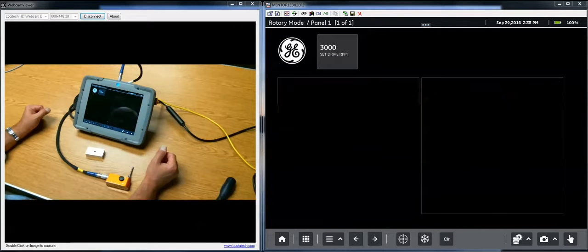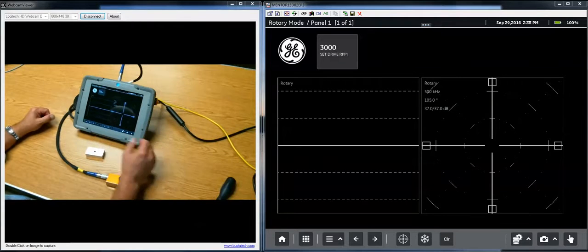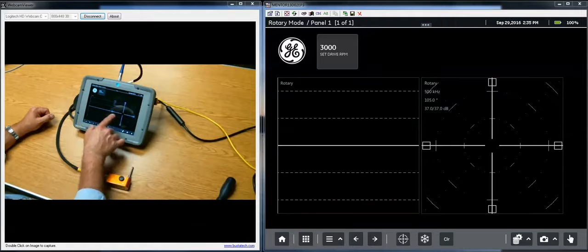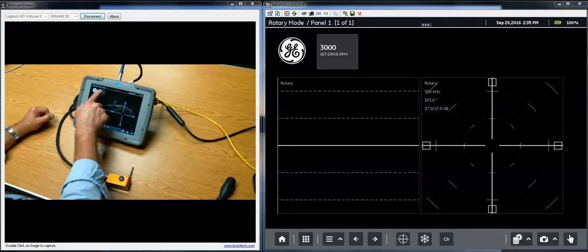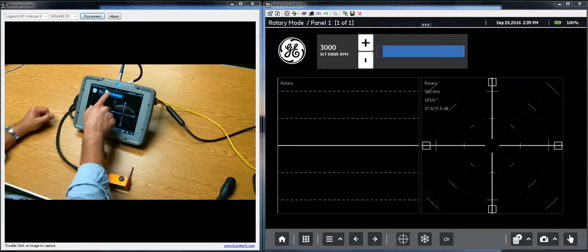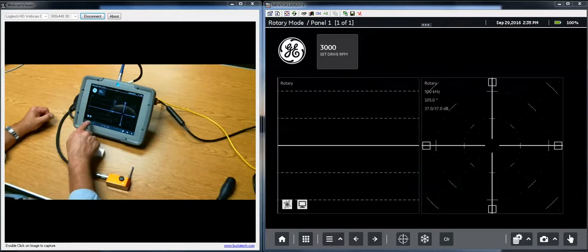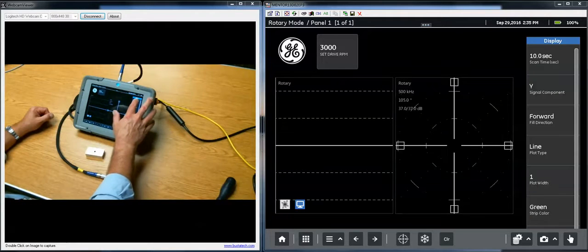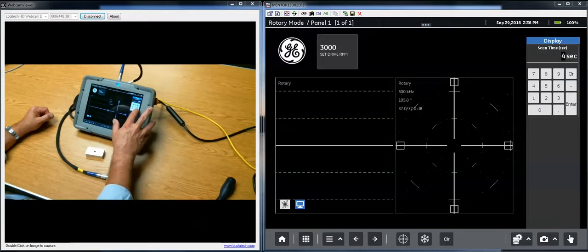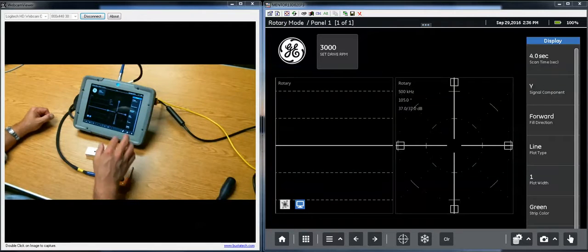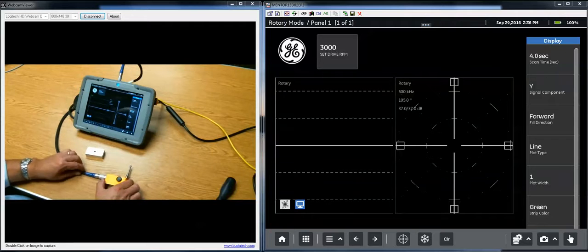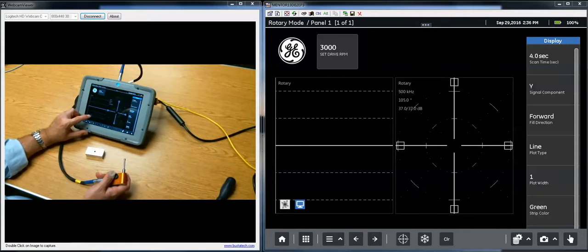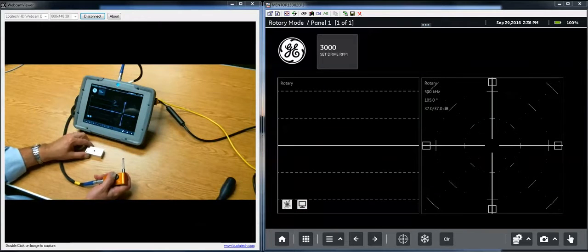As we launch the Rotary mode app, very simple layout. We have a time-based view on the left. We have a lissajous or impedance plane view on the right. We have a control at the top of the screen to adjust the rotational speed of the drive. On the strip chart, we're going to reduce the buffer time, the scan time, a little bit. We tend to collect a tremendous amount of data in rotary mode, so shorter scan buffers are a little easier to deal with here. And the strip chart is going to work differently in rotary mode.